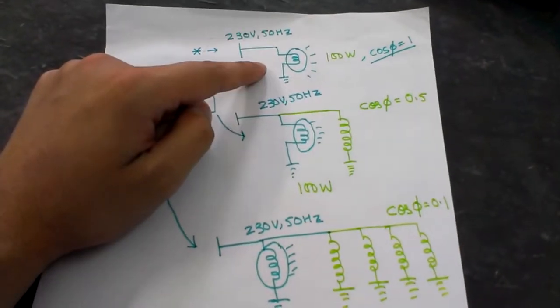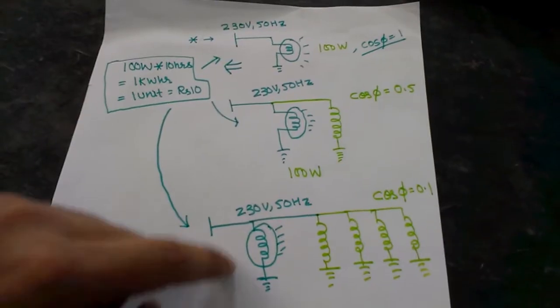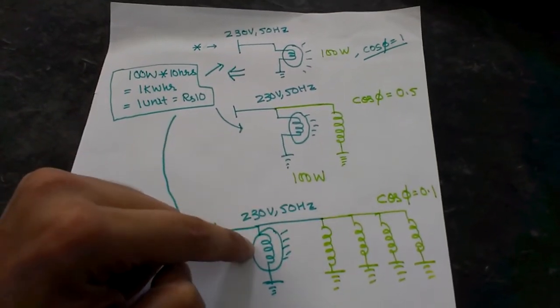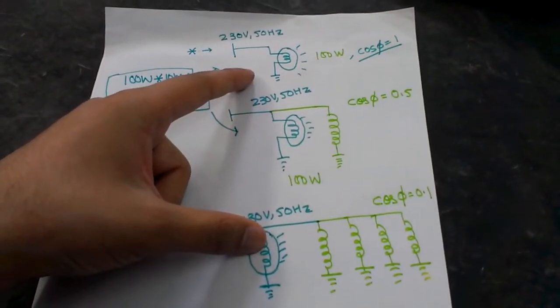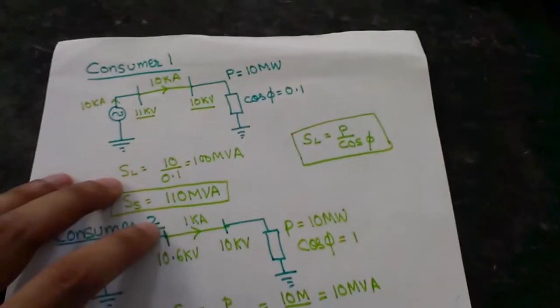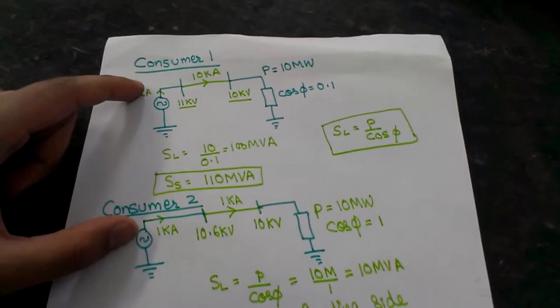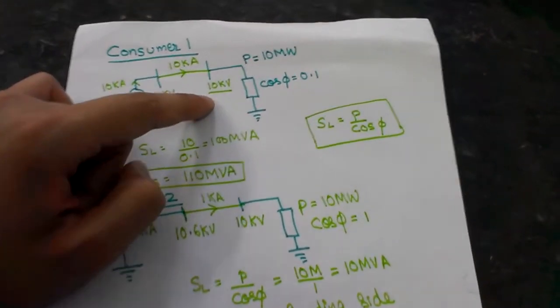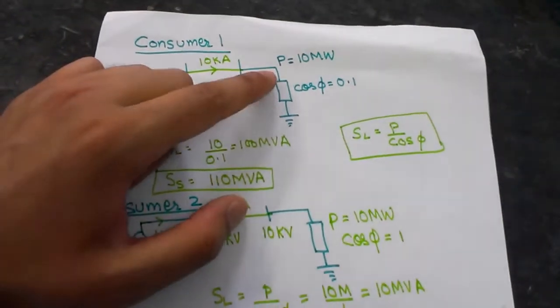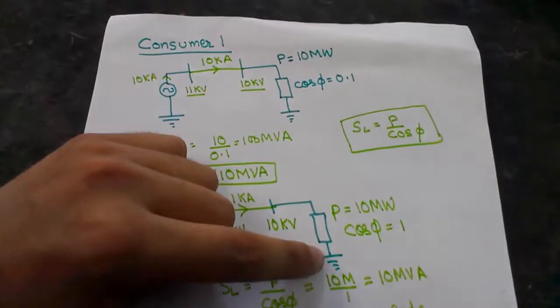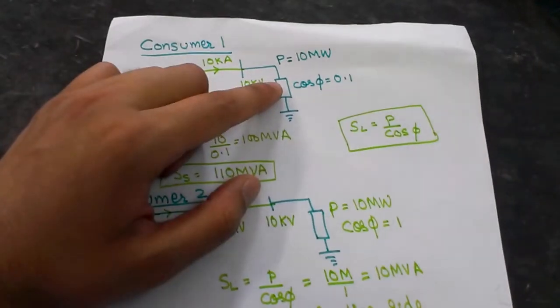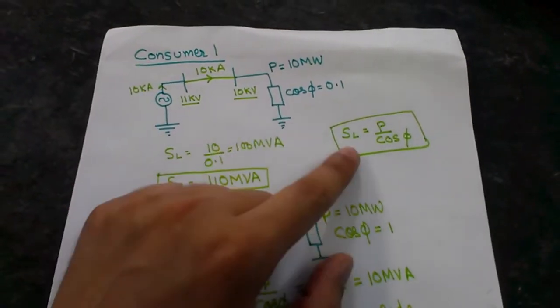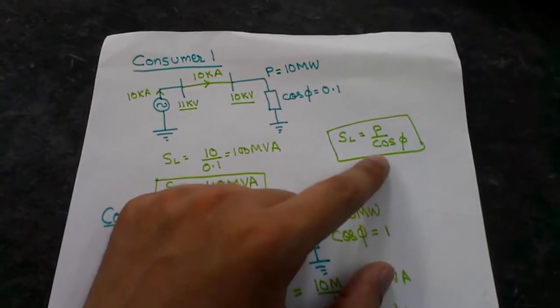No — we know that the two customers with poor power factor have to pay more compared to the first customer. Although they are consuming the same real power, what extra facility is being provided to these customers that causes them to be charged more? Now I'm considering two big consumers. The power utility is providing 10 kilovolts in both cases, and both are consuming 10 megawatts each. The power factor is 1 in one case and 0.1 in the other. The total apparent power S = P / cos φ = 100 MVA in the low power factor case.